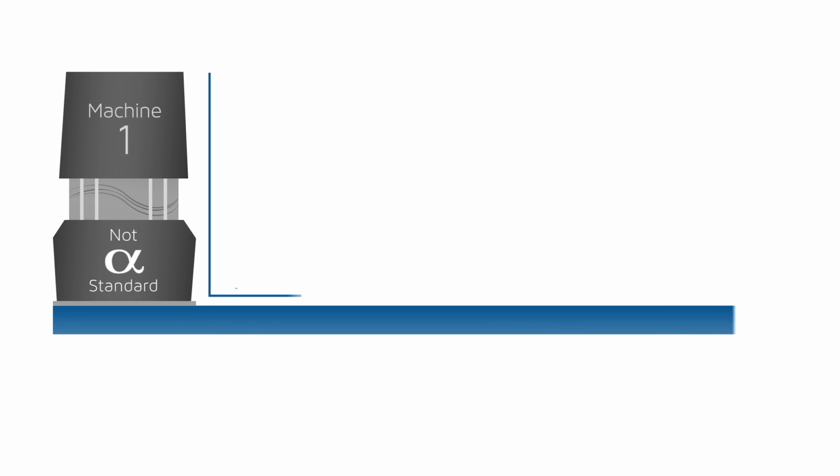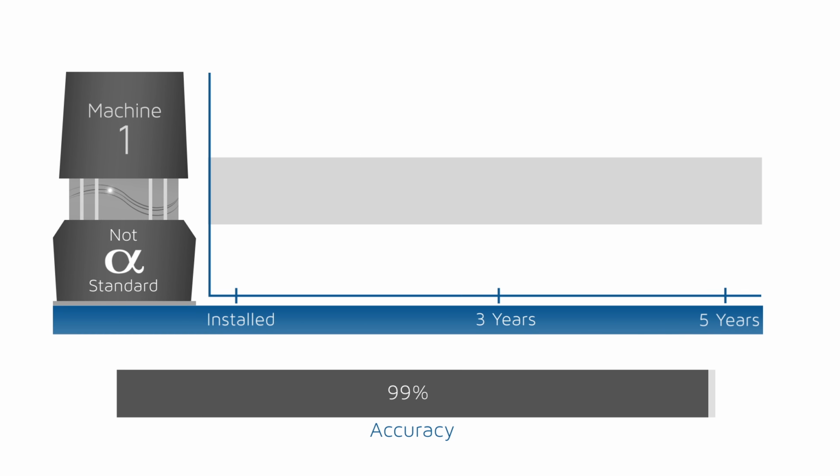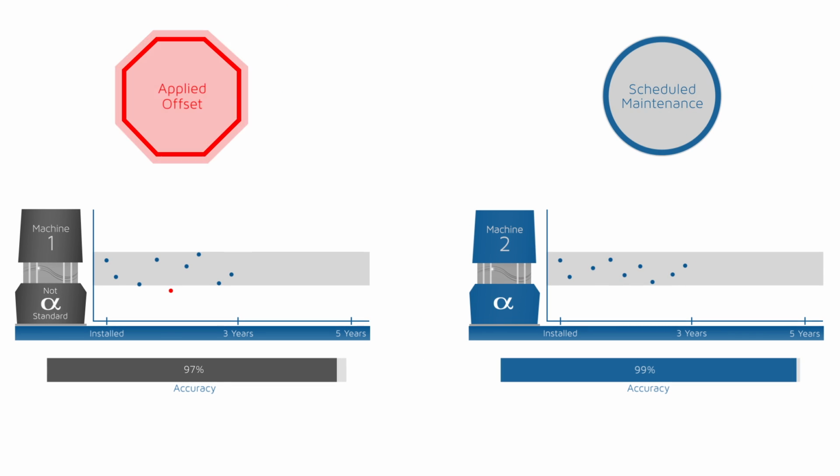With ever-increasing demands on product performance, it is important to remember that a testing instrument is only as good as its data precision. Like all machinery, it is subject to wear and tear, which ultimately leads to performance variations. This being an industry-wide occurrence, some instrument manufacturers use inferior methods, such as a correction factor or an offset, in an attempt to skew data back into a range that is artificially within spec. This can lead to safety hazards due to equipment malfunction, false positive test results, and ultimately, inferior quality products.